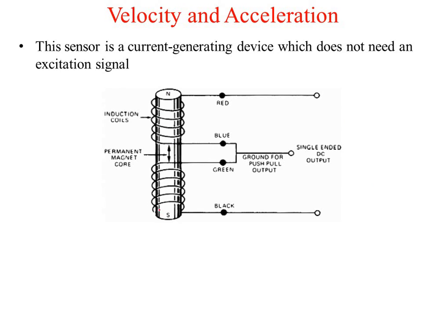Now for this N and S pole, when it is at the center and no movement is there, the output voltage generated will obviously be 0, because V1 will be generated over here, let us consider, and V2 over here, so V1 and V2 are equal. But when you move this either upward or downward, the flux linkage with coil 1 and coil 2 will be different, and that is going to vary V1 and V2.